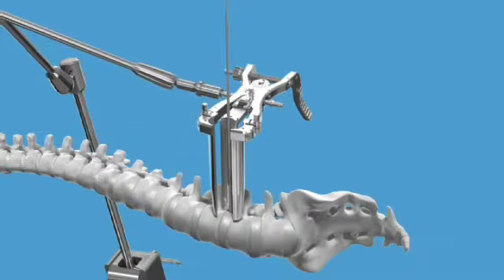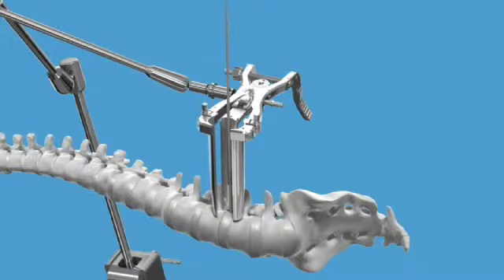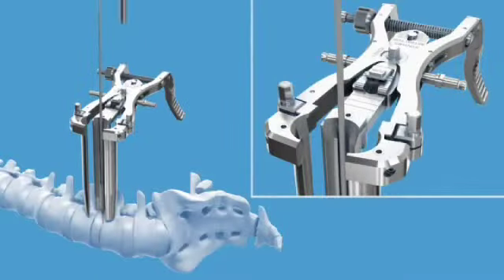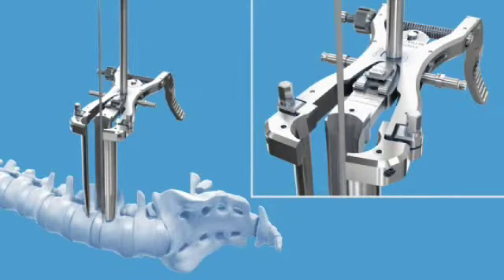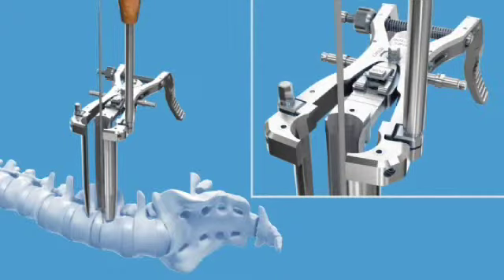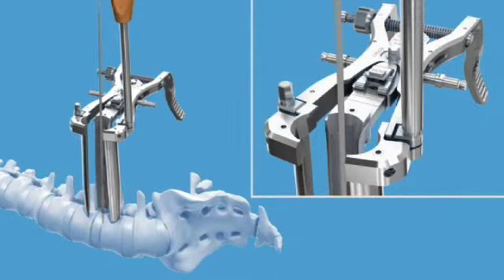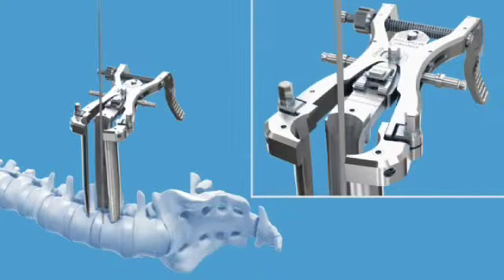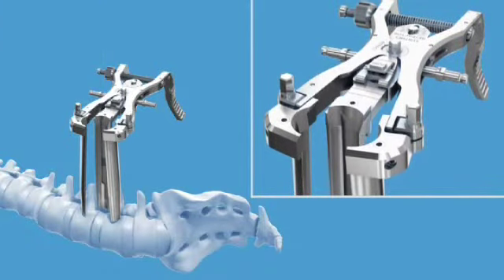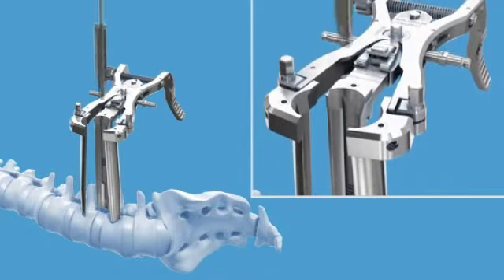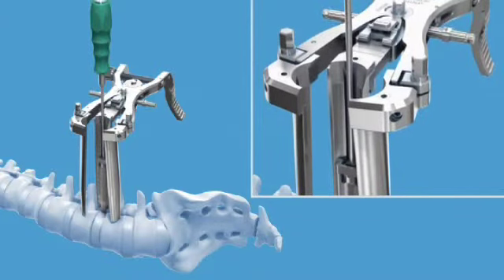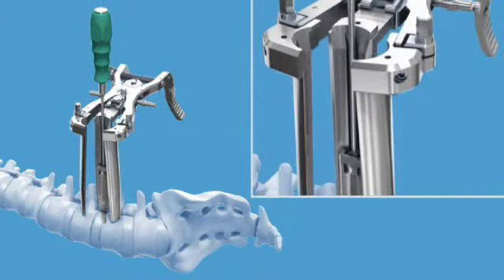Use the universal arm and table clamp to stabilize the retractor to the OR table. Gently retract the third blade posteriorly by turning the knob clockwise with the socket wrench. With the blades open and secure, slide the light clip onto either the cranial or caudal blades of the retractor. For further retraction, the cranial and caudal blades can independently provide up to 15 degrees of angulation. When the desired angulation is achieved, remove the probe. For increased retractor stability, attach the intradiscal anchor to the third blade by screwing the anchor onto the extension driver and sliding the anchor down the grooves of the third blade.